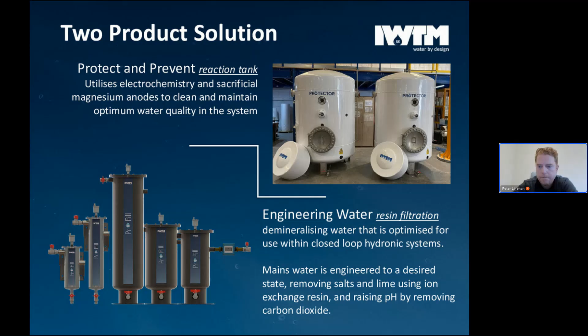Now, the good thing about chemical-free water treatment is that it's completely scalable. Our smallest unit, our P1, can do 1,000 litres of LTHW, but for cooling systems it can only do 650. The reason is that the cooler the temperature of the water, the more dissolved oxygen it will have, so it needs more magnesium anodes. That's why we have a lower limit on cooler temperature systems.